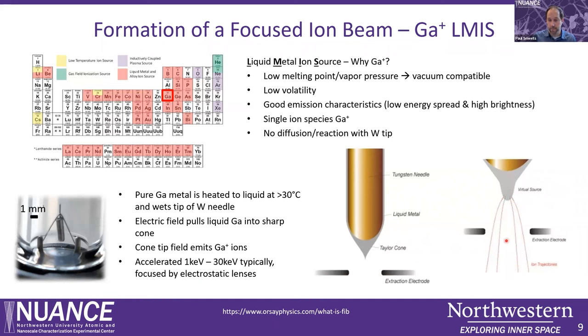The largest advantage gallium has is that when heated to just about room temperature on a tungsten needle, it can form a so-called Taylor cone — a virtual source about 10 to 15 nanometers in diameter. When submitted to an electric field, positively charged gallium ions are emitted towards the sample and accelerated typically from 1 to 30 kV. These gallium ions are focused by electrostatic lenses, not electromagnetic lenses as in an SEM, and then interact with the sample.